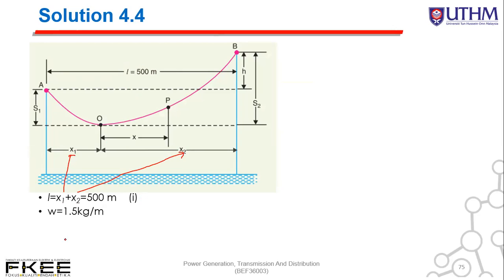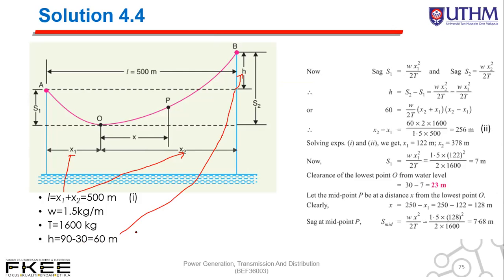Then given weight equal to 1.5 kg per meter, also tension 1600 kg. And H is the difference between tower B and tower A. So we get H is 90 minus 30 equal to 60 meter. Then we calculate the sag for S1. We have two formulas: sag S1 uses Wx1 square over 2T, and sag S2 is Wx2 square over 2T.